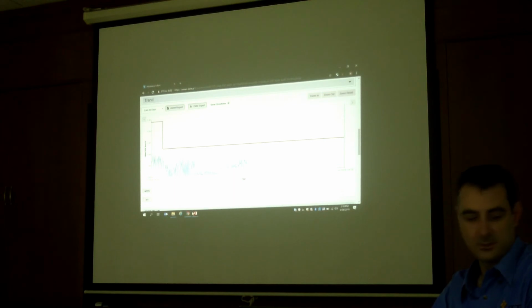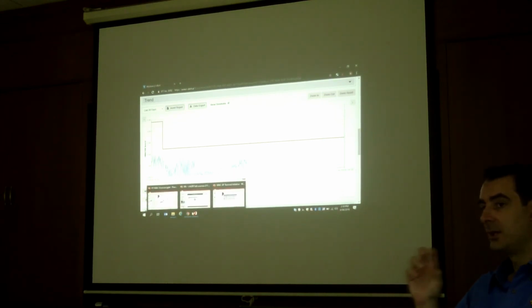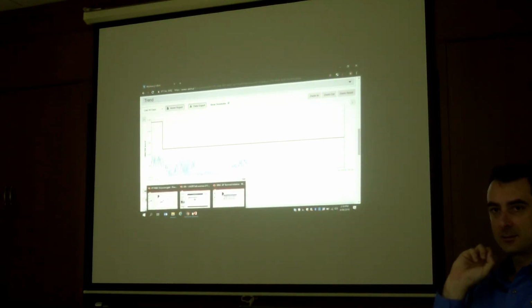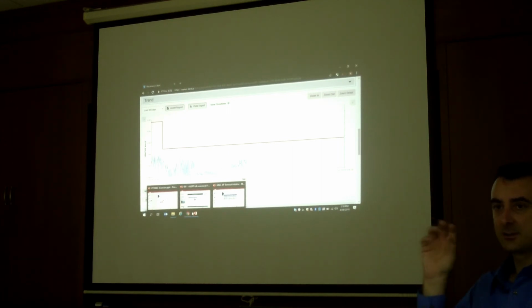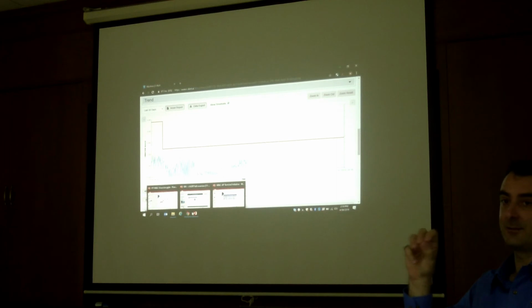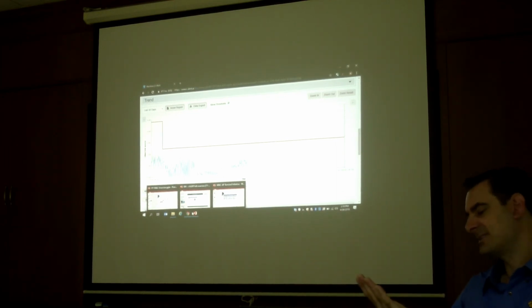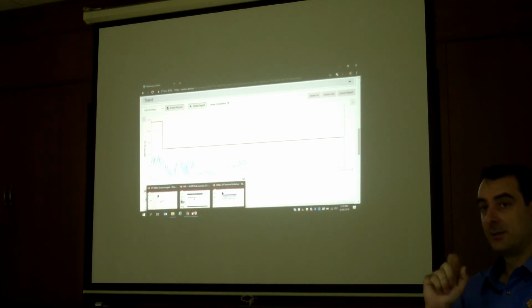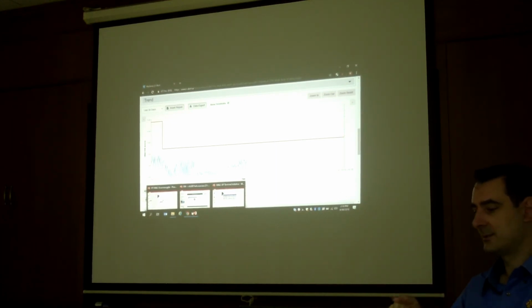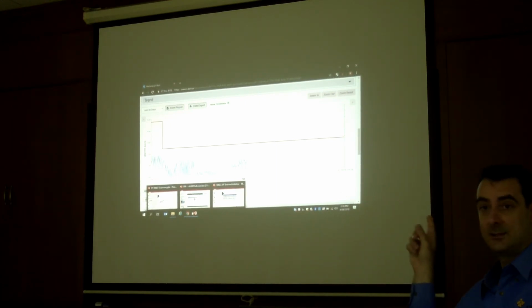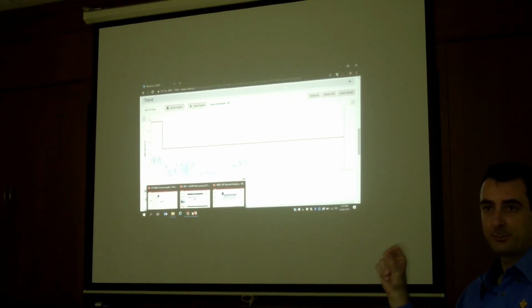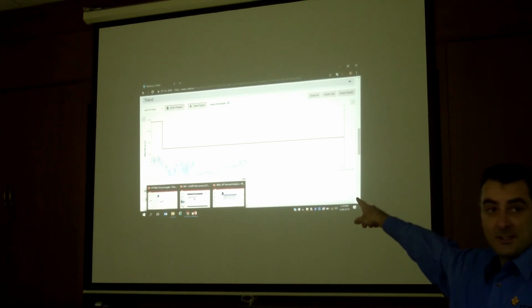So each iAlert is always sending out the status, red, yellow, or green. Also, it always sends out the last vibration reading, always. Your phone, you can't see it until you click on it. But the gateway will see it, and it will put it straight in here. So every hour when a new piece of data is provided, it will just appear here.